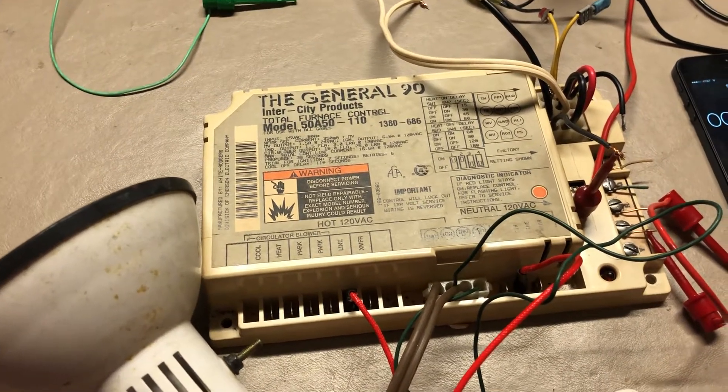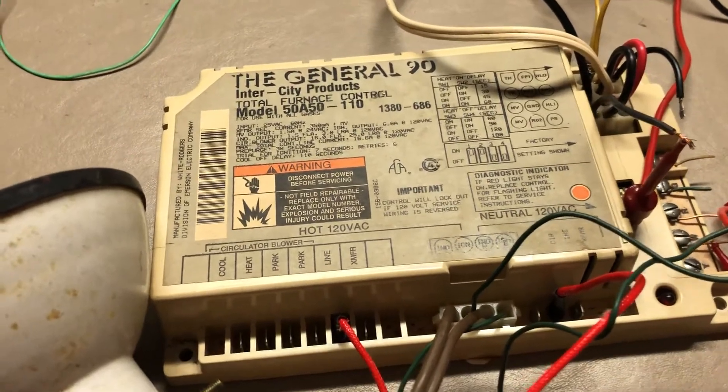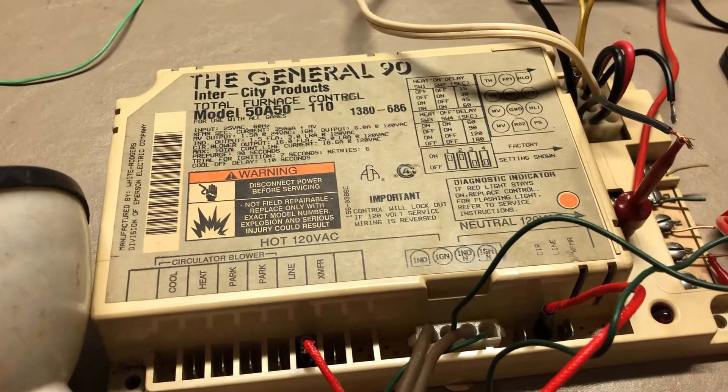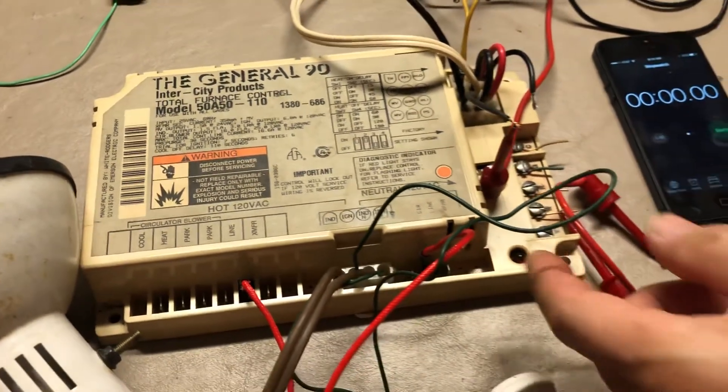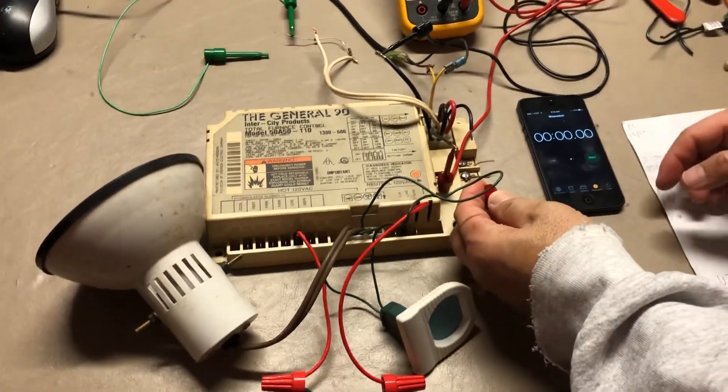This is a functional test on my test bench of the General 90 model 50A50-110 furnace controller. First, we're going to call for heat and jumper the R and W button contacts.